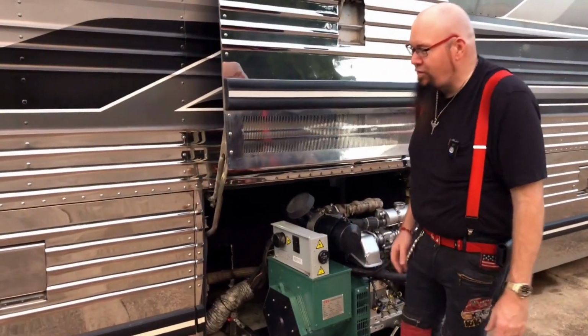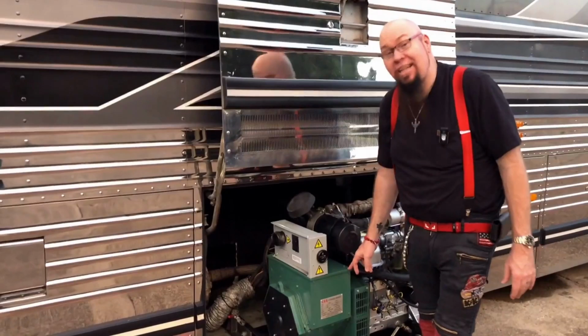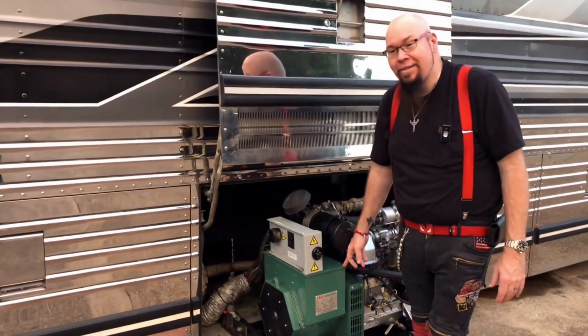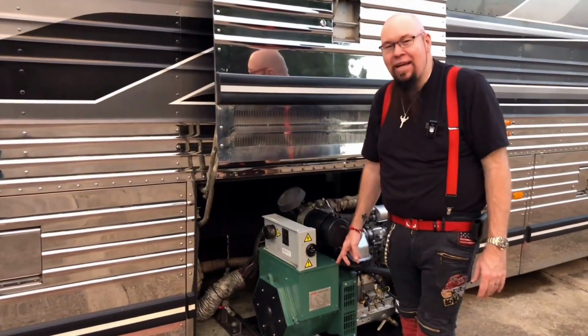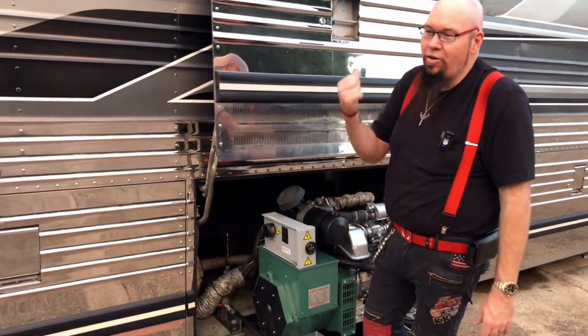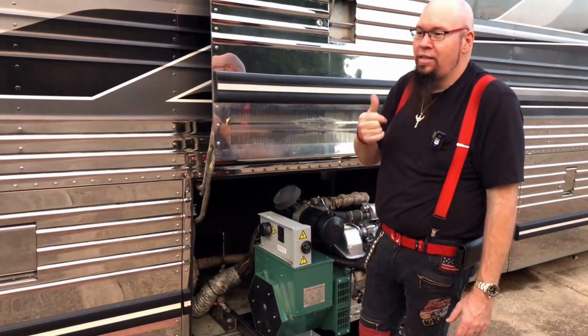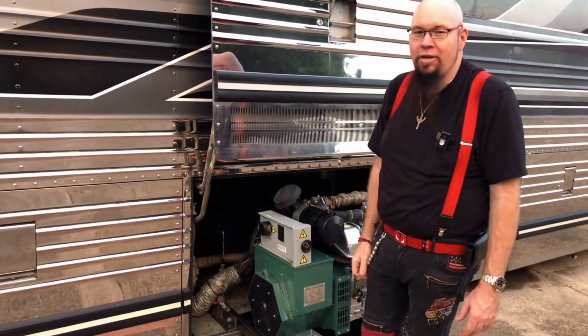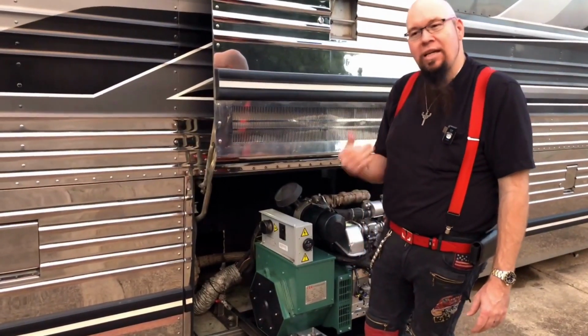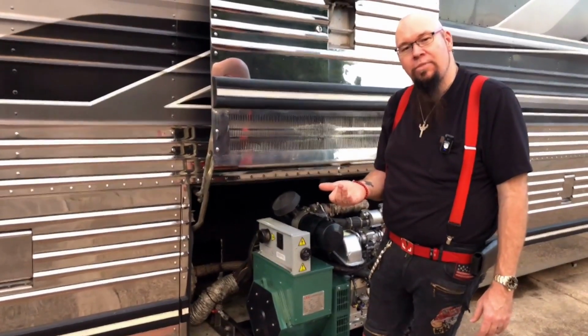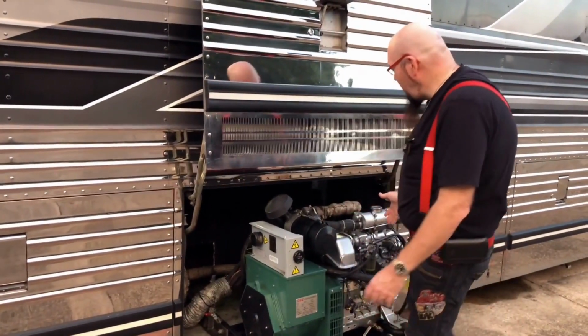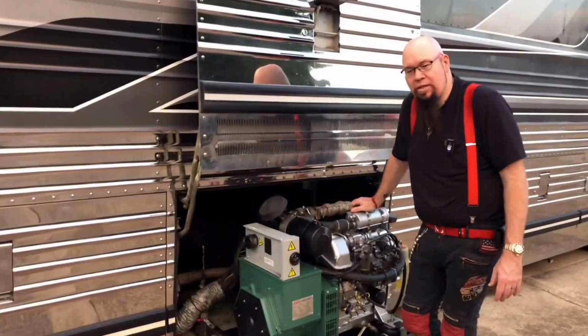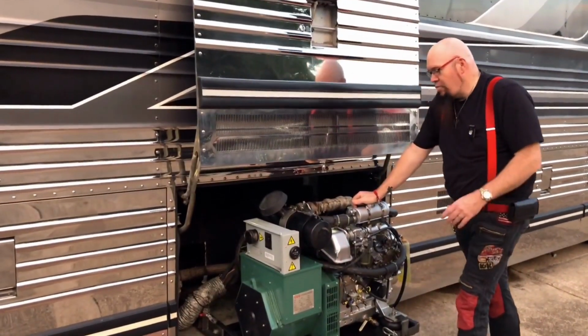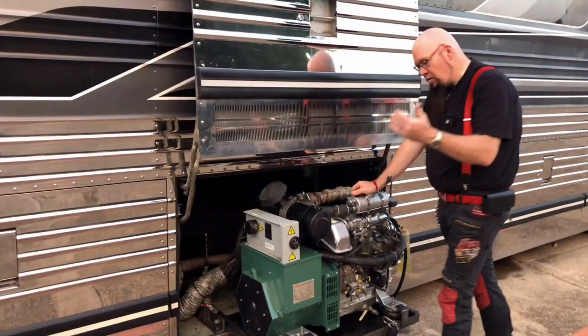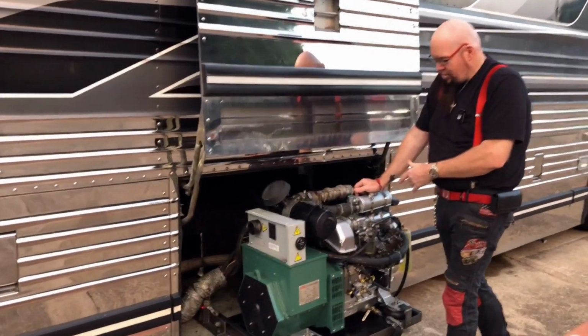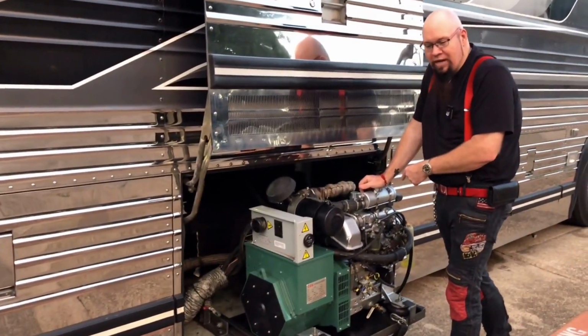The reason you put that in there is for some yahoo that might hook this thing up to a gasoline engine. Bad idea, don't hook it up to a gasoline engine. I mean, I thought about it. I've got a 4-cylinder Volvo motor sitting around that was in a crash car, and I thought that would make a good generator. But gas engines run up to 6,000 RPMs and they don't have the same amount of torque. Diesels only run about 2,000 RPMs, maybe 2,200 before they blow themselves up, maybe 2,500 for some units. This thing running at 1,800 RPMs is as fast as it's going to go, and that's where you want it.